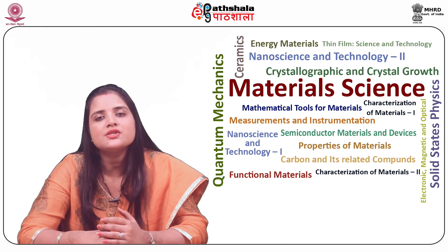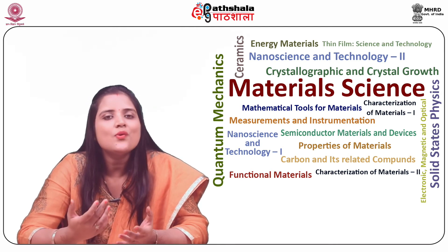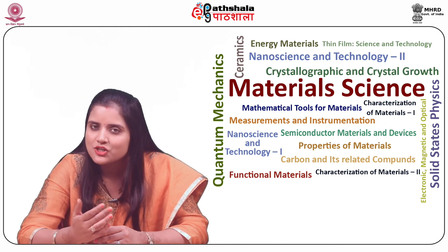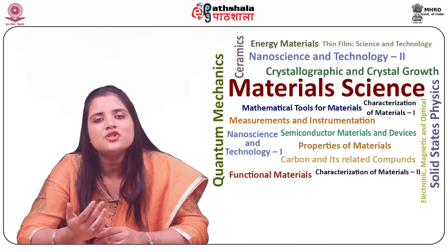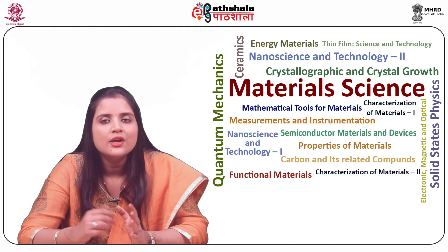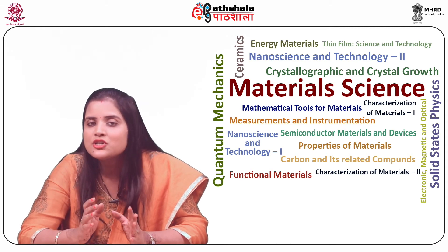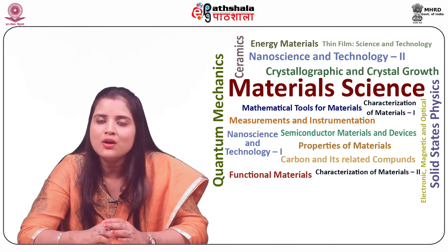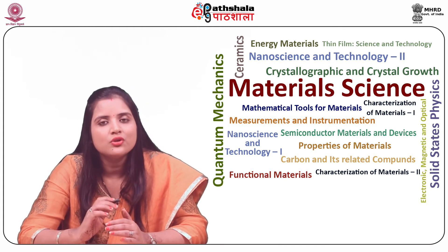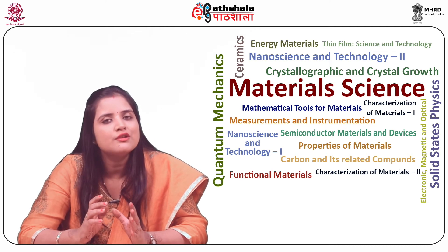Let us study about monochromators. There are two types of monochromators: excitation and emission monochromators. Entirely reflective optics are used to maintain great resolution over the full range of spectrum as well as to reduce spherical aberrations and re-reflection.